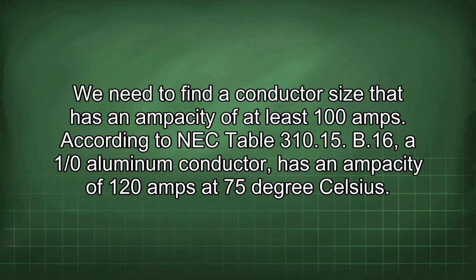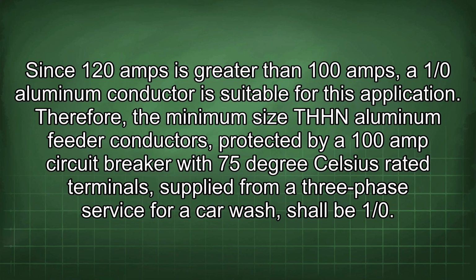According to NEC Table 310.15(B)(16), a 1/0 aluminum conductor has an ampacity of 120 amps at 75 degrees Celsius. Since 120 amps is greater than 100 amps, a 1/0 aluminum conductor is suitable for this application. Therefore, the minimum size THHN aluminum feeder conductors protected by a 100 amp circuit breaker with 75 degrees Celsius rated terminals supplied from a three-phase service for a car wash shall be 1/0.